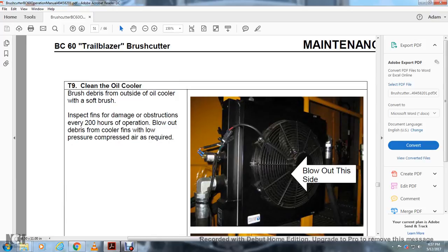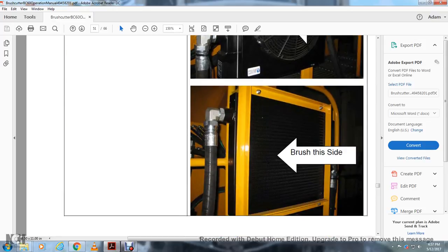T9, cleaning the oil cooler. Brush debris from the outside of the oil cooler with a soft brush. Inspect the flat fins for damage or obstruction. Every 200 hours, blow out the debris from the cooler fins with low pressure compressed air as required. Blow out this side. Brush this side.